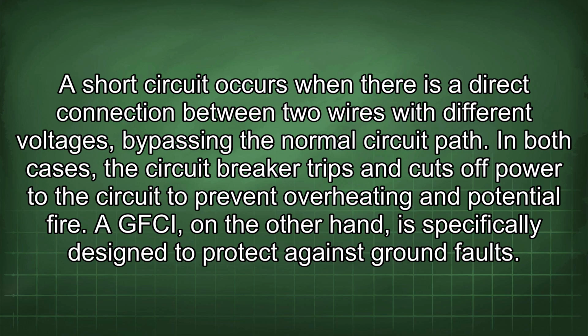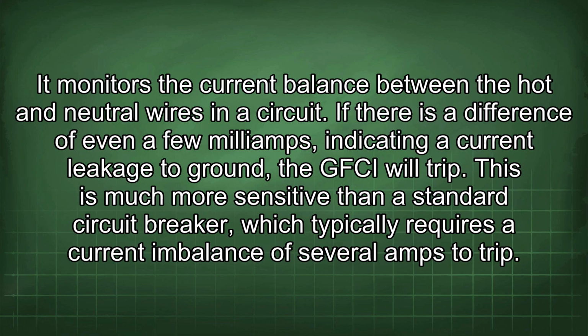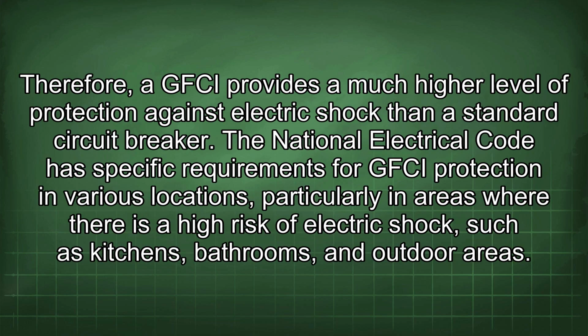fire. A GFCI, on the other hand, is specifically designed to protect against ground faults. It monitors the current balance between the hot and neutral wires in a circuit. If there is a difference of even a few milliamps, indicating a current leakage to ground, the GFCI will trip. This is much more sensitive than a standard circuit breaker, which typically requires a current imbalance of several amps to trip. Therefore, a GFCI provides a much higher level of protection against electric shock than a standard circuit breaker.